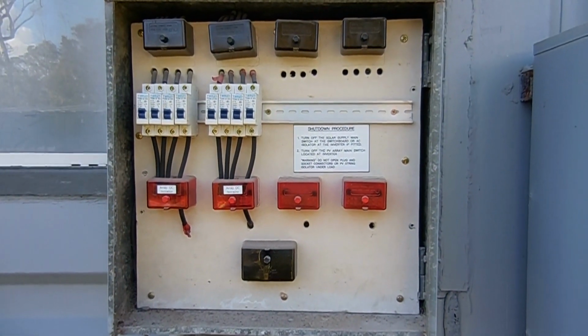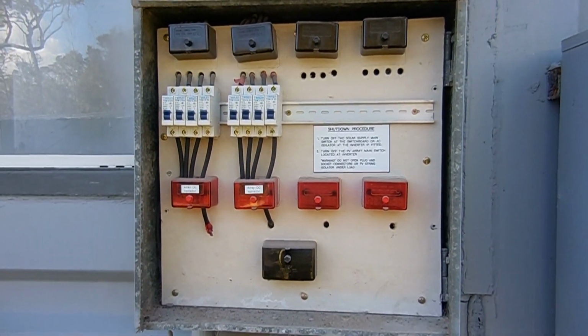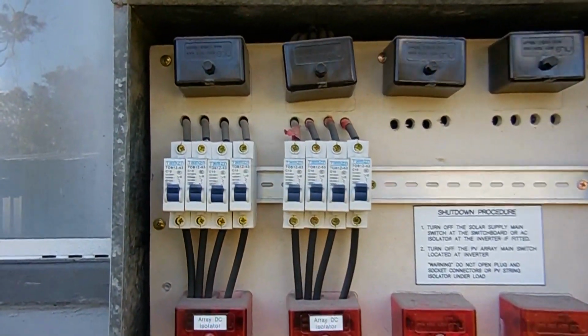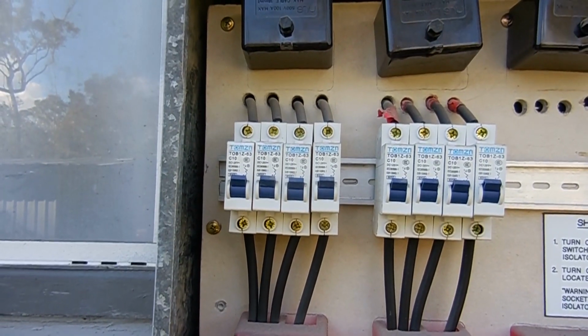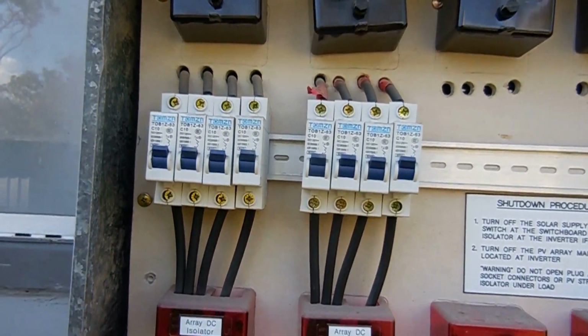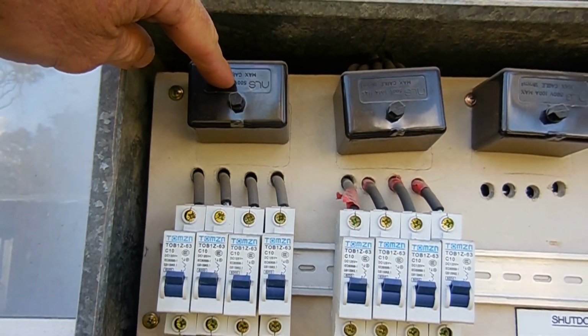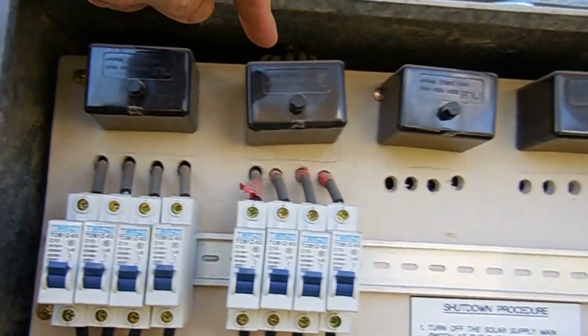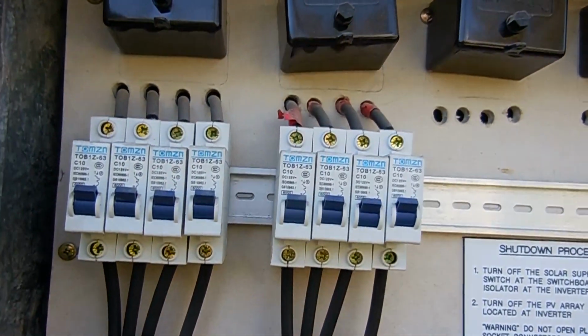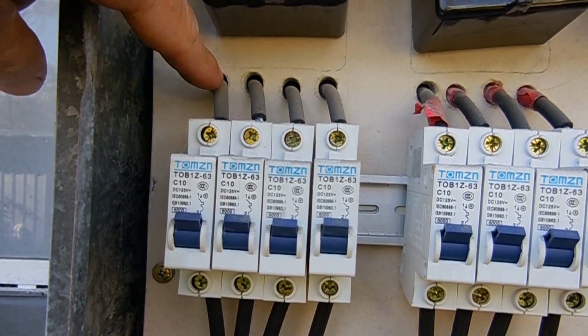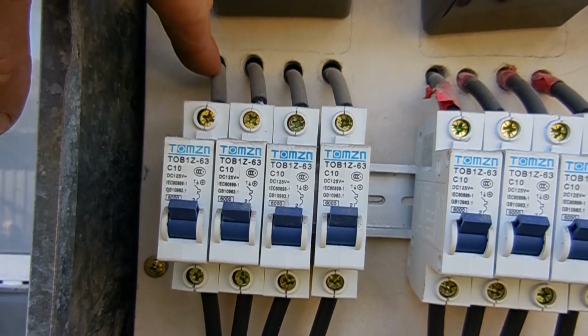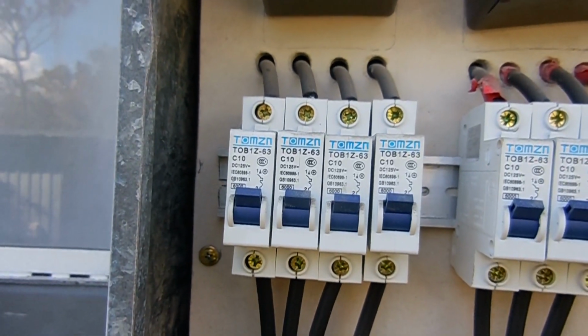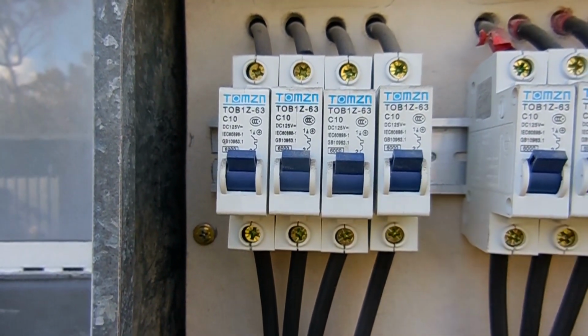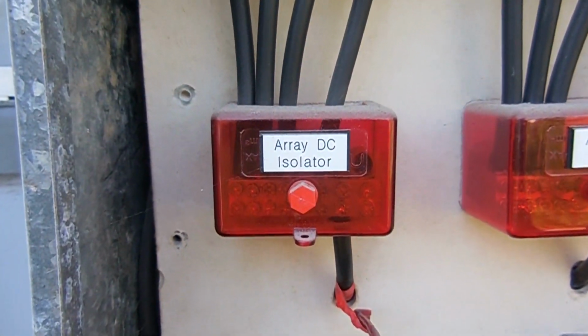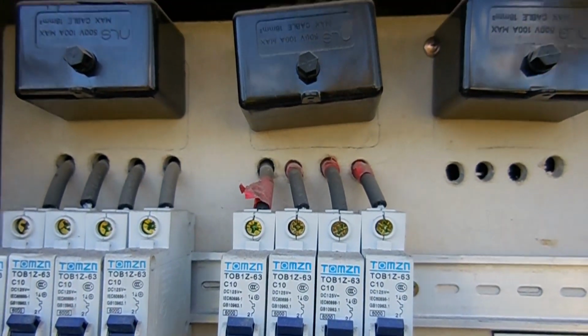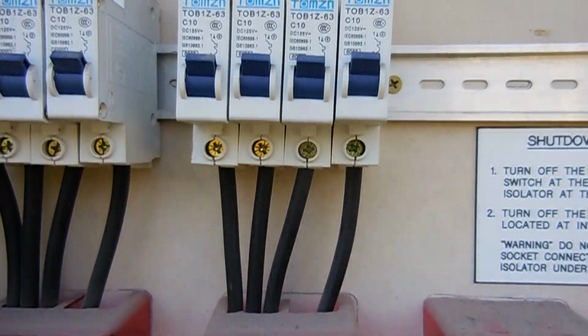Well, here we are at the combiner box. This is where all the solar panels, the series string of solar panels, come down to combine. This group of breakers here, this is the first 2 kilowatts, and here is the 3 kilowatts. So we've got the negative terminals here, they're all combined, and the negative terminals there for the 3 kilowatts. So you can see for the 2 kilowatts, that's a set of 3 panels. These are the positive wires. So set of 3, 3, 6, 9, 12 makes up the 12 panels. And they go through an individual breaker each, and then they're combined here at this bus bar. And the same with the 3 kilowatt set of panels.